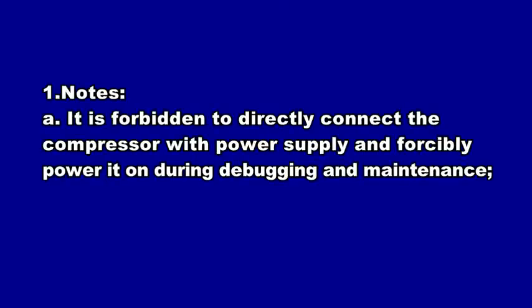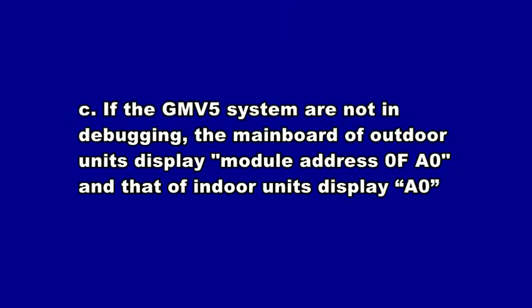Unit commissioning. First, notes. A. It is forbidden to directly connect the compressor with power supply and forcibly power it on during debugging and maintenance. B. Debugging must be performed on the GMV5 system before system operating. C. If the GMV5 system is not in debugging, the main board of outdoor unit displays module address of 0F-A0 and that of indoor unit displays A0.